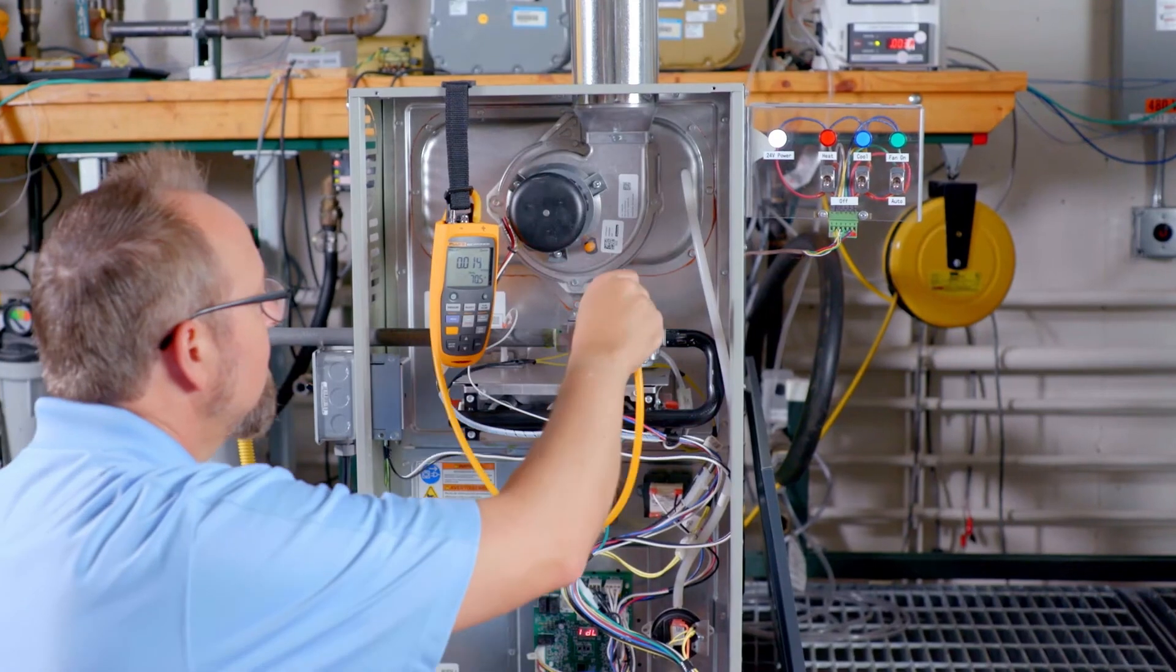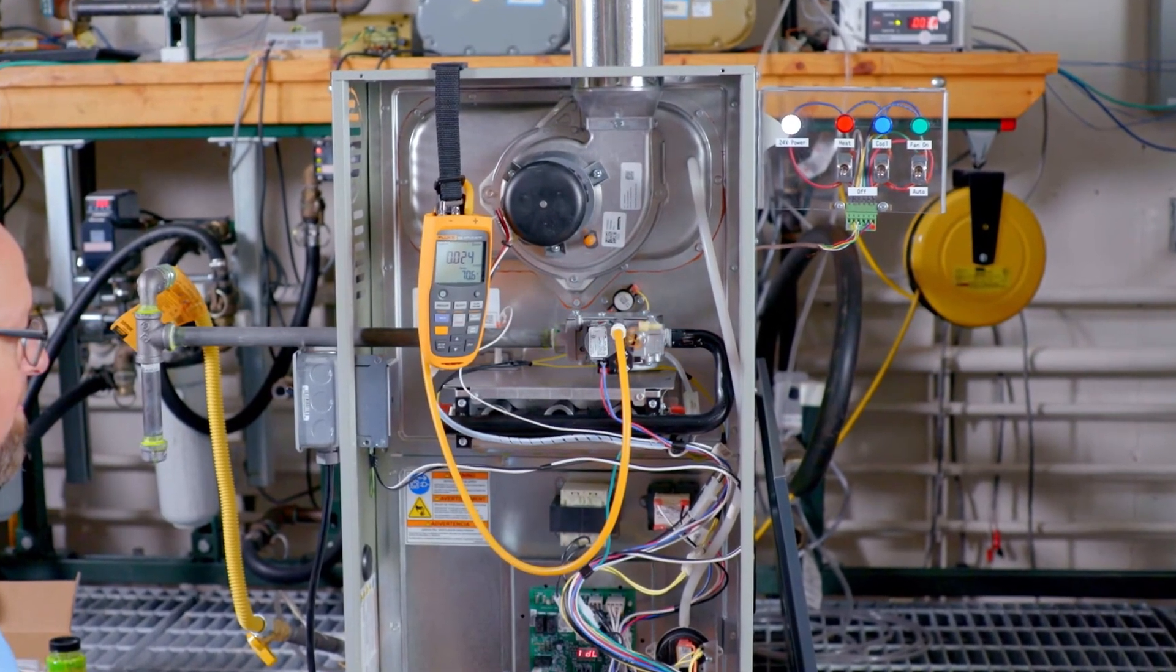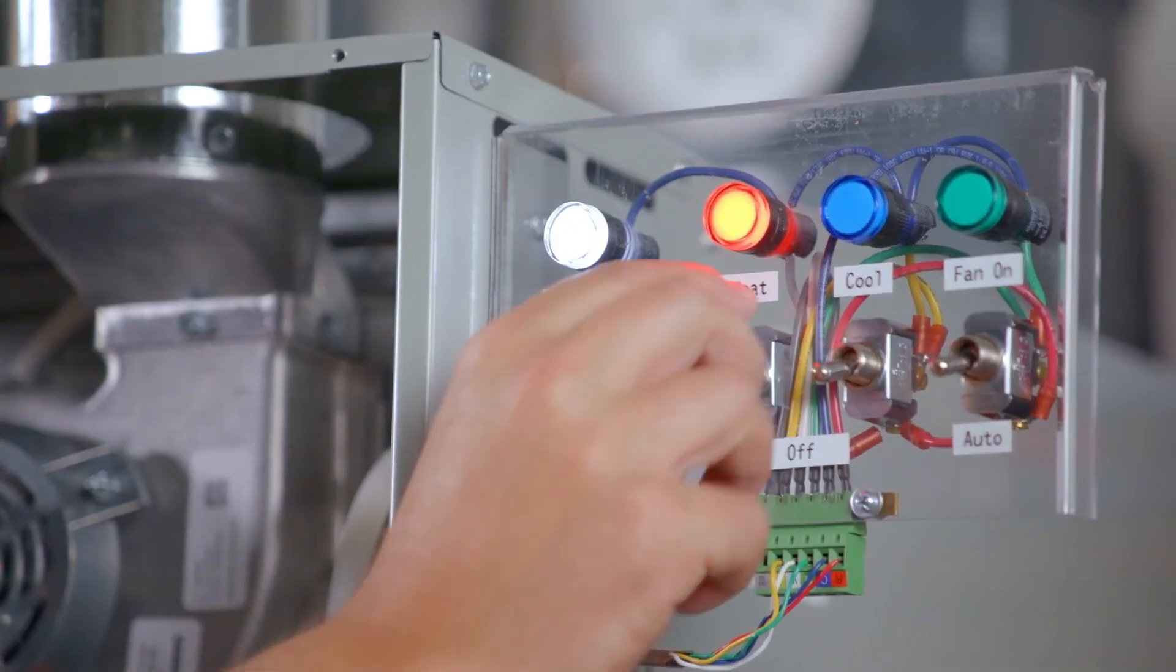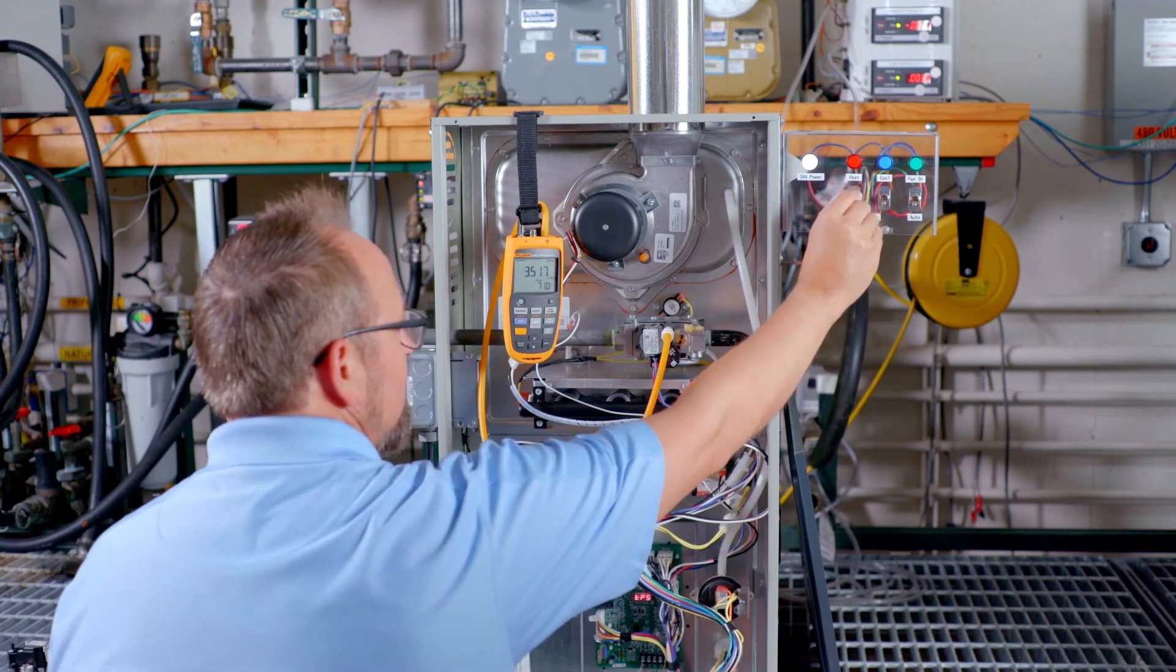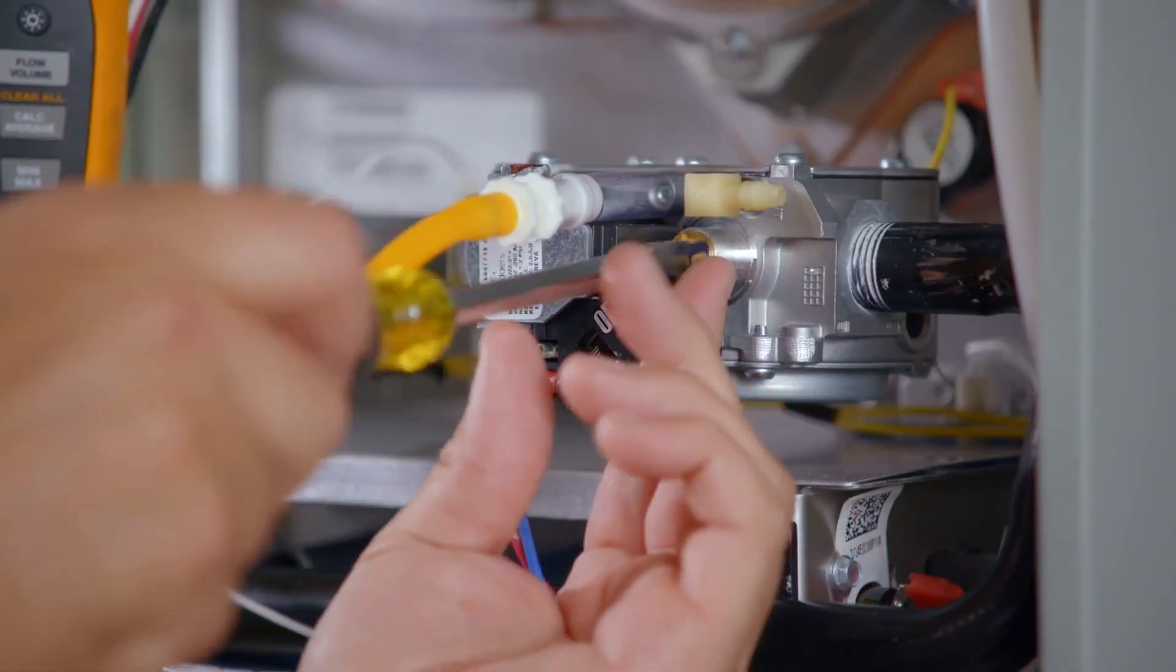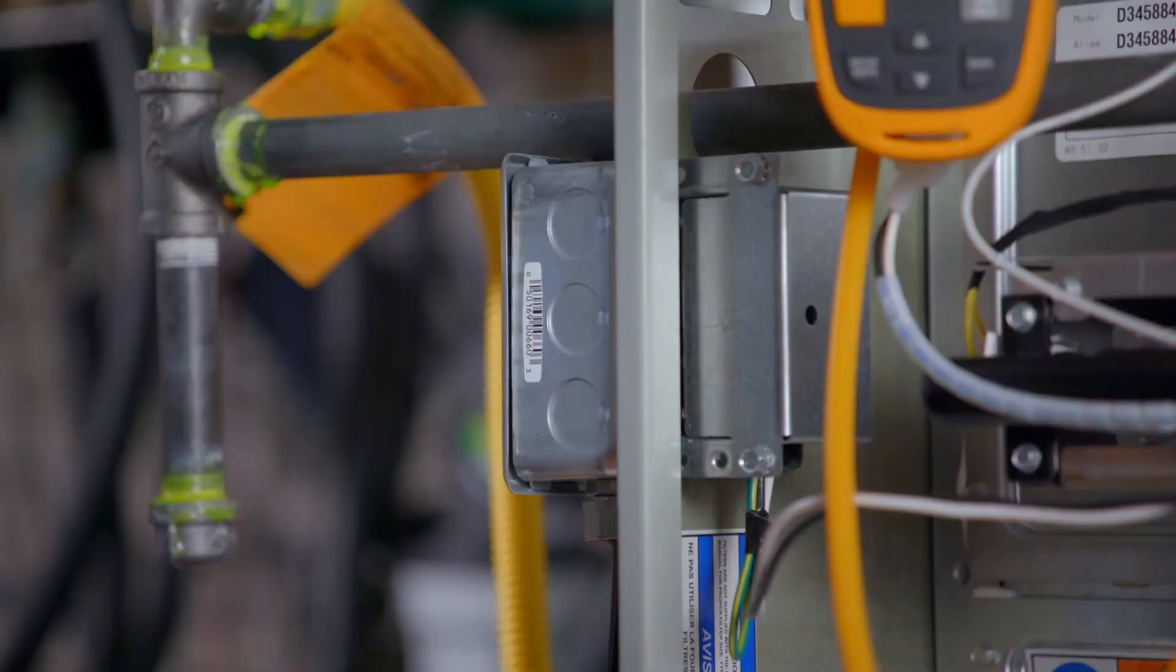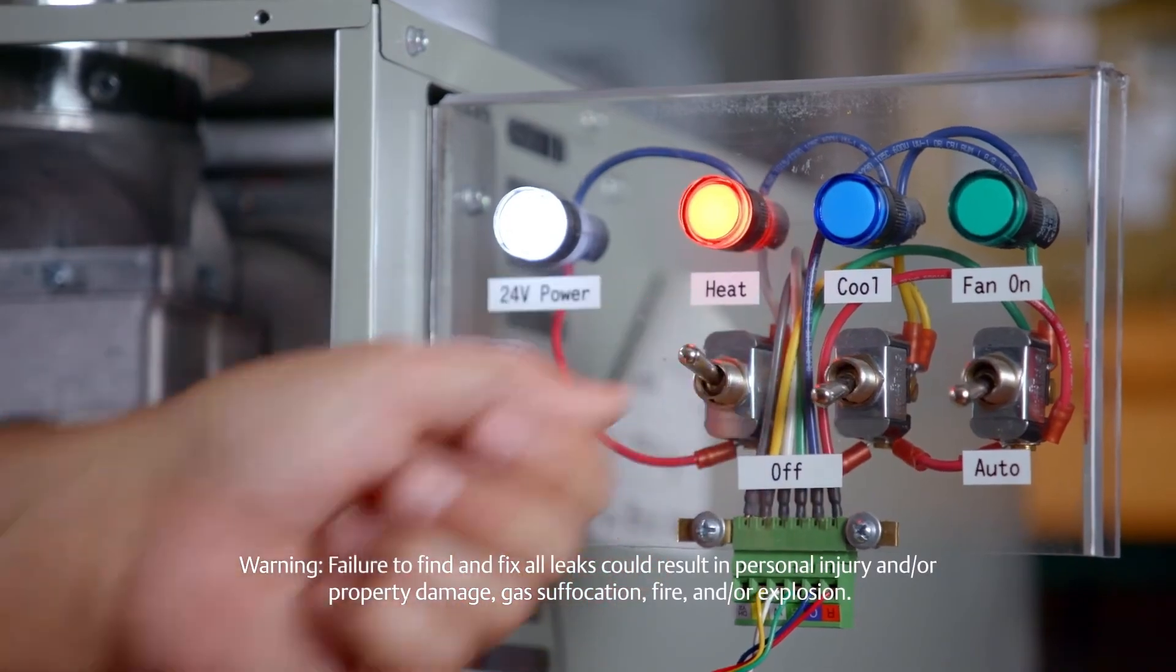Once the gas pressure is set, finalize any additional tests desired and terminate the call for heat. Turn power and gas back off. Replace the regulator cover screw. Disconnect the gas manometer and turn the outlet pressure test screw clockwise to seal the pressure port. Restore the electrical power and gas to the unit. Make a call for heat and wait for the gas valve to be energized.